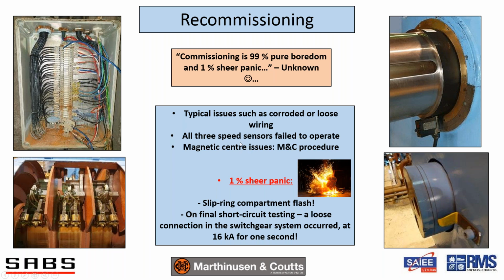Then because the 2 machines, the drive motor and the generator, are connected with a solid coupling, it's important to make sure that the axial magnetic center of the drive motor ties up with the magnetic center of the generator. And we developed a procedure to do that without actually fully exciting the machines, which ended up being quite useful. So what was the 1% shear panic?